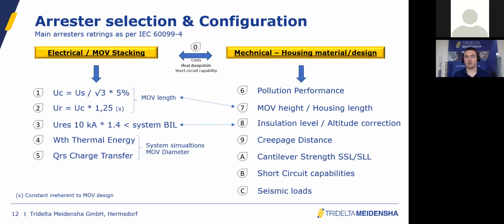Then comes the mechanical requirements. The IEC standard for surge arresters, 60099-4, defines two important ratings for mechanical strength. The first is SSL, the specified short-term load. It has to do with the dynamic force coming, for example, from seismic events or short circuit. Then comes the SLL, the specified long-term load, which has to do with a static load, mainly coming from the conductor weight. Then we have the short circuit capabilities and the seismic loads, which are also important for the housing selection.